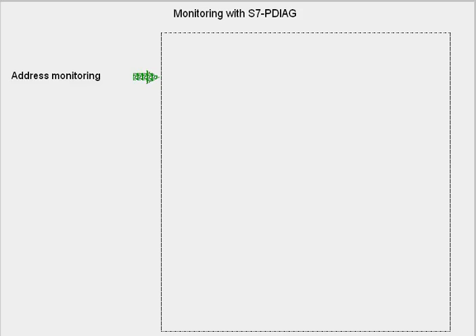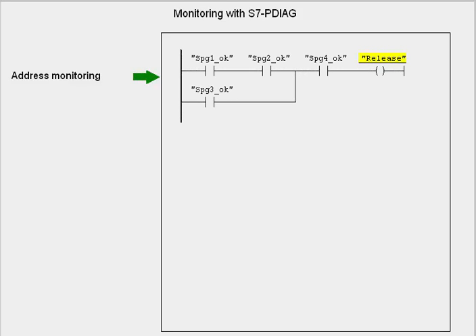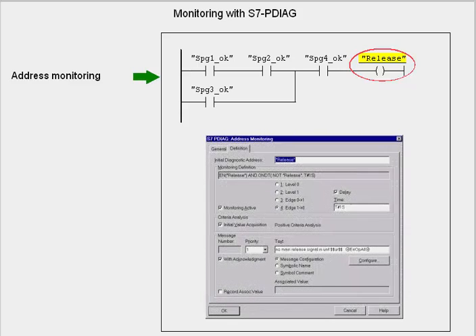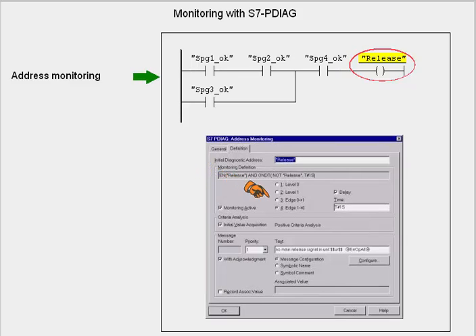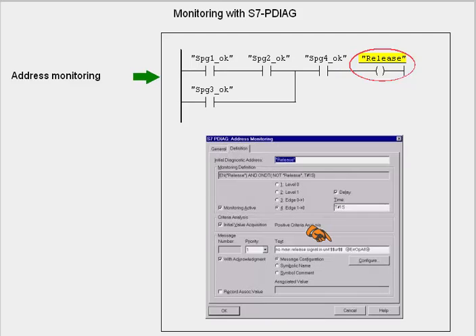Using address monitoring, you can monitor specific addresses in the program or directly from the symbol list on a set point level or change of edge. The task of the configurator is to attach the error definition to an assignment in the desired network and to parameterize the predefined monitoring logic in a dialog. You have a choice here of edge or level monitoring combined in each case with a delay time. You can add parameters and any associated values to the message text that is supposed to be displayed in case of fault.